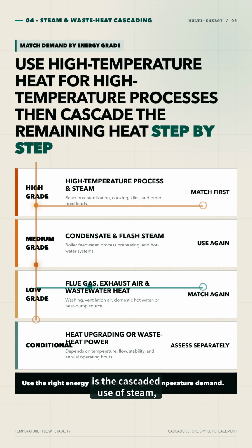The fourth type is the cascaded use of steam, hot water, and process waste heat. High-temperature heat should serve high-temperature processes first. Condensate, flash steam, low-temperature flue gas, and exhaust air heat can then be matched in sequence to preheating, cleaning, space heating, ventilation air, and domestic hot water. In boiler houses, kilns, dryers, paper mills, textile plants, chemical sites, and food factories, this system-level approach often creates more value than replacing one machine with a more efficient model. If the waste heat temperature is too low, a heat pump can raise its grade. If both temperature and scale are high enough, waste heat power generation may be evaluated, but it is not suitable for every factory. Temperature, flow, stability, and annual operating hours are all essential.